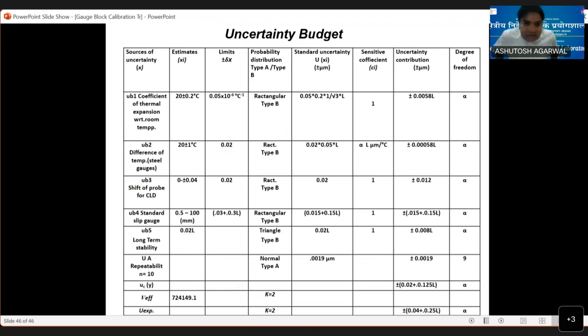This is the uncertainty budget. We take all these, and the gauge block is one of the finest examples. Anywhere, if somebody wants to discuss the uncertainty of anything, then the gauge block is one of the most preferred and widely used, because it covers all the parameters: change in temperature, change in temperature of the two, and so on.